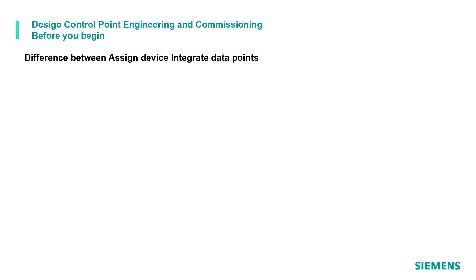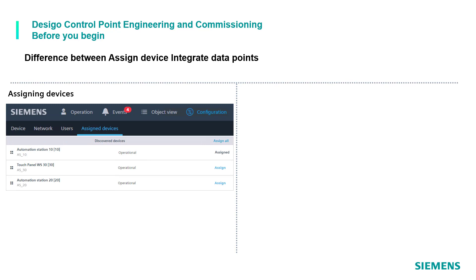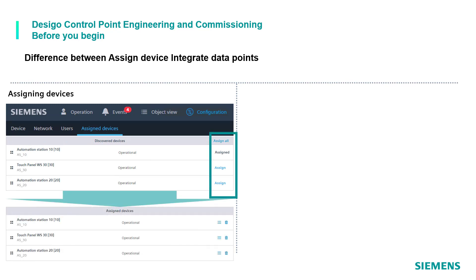What is the difference between assigning devices and integrating data points? When we talk about assigning devices, we refer to which devices in the physical BACnet network should be linked to a specific Desigo Control Point device for general access and generic operations.